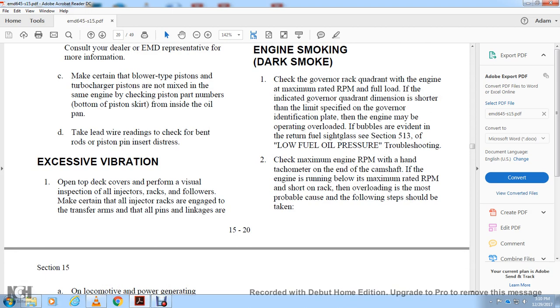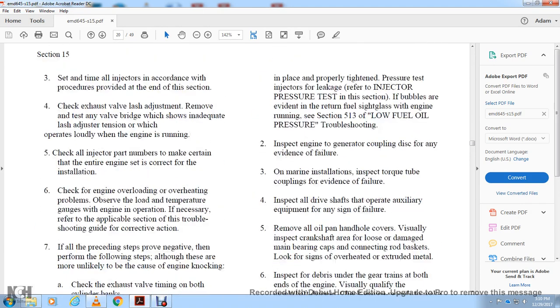Excessive Vibration on the Top Deck: Perform a visual inspection of all injector racks and followers. Make certain all injector racks are engaged with the transfer arms and that all pins and linkages are properly in place. Pressure test injectors for leaks — refer to the injector pressure test section. Check for bubbles in the return fuel sightglass with the engine running, and refer to Section 513 low fuel oil pressure troubleshooting. Inspect the engine-to-generator coupling for signs of failure. On marine installations, inspect the torque coupling for evidence of failure. Inspect all drive shafts operating auxiliary equipment for any sign of failure.